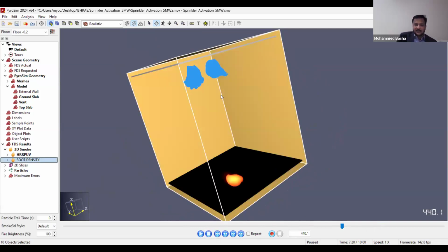What is the smoke density there? Oof, it's full. So still I used 5 megawatt here. So I need to use more because the height is more. So by considering Q as 5 also, it is not working by using Alpert's correlation. With Alpert's correlation, you have to use CFD analysis also to check whether the smoke is traveling down or not before you activate the smoke extract system. No, at 440 seconds, still it did not. Just now the sprinkler got activated, the water has still not reached here, but the smoke is already down. So the fire size we need to consider in Alpert's correlation equation should be way bigger.